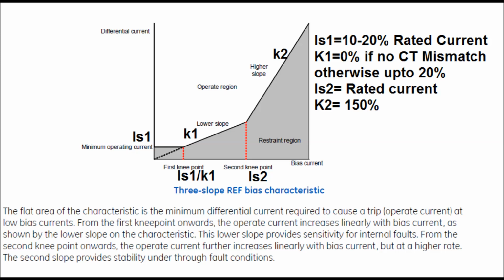From the second knee point, that is IS2, the operate current further increases linearly with bias current, but at a higher rate. Normally IS2 is set as the rated current of the winding under protection. The second slope provides stability under through fault conditions. Normally K2 is set as 150%, that is 1.5.